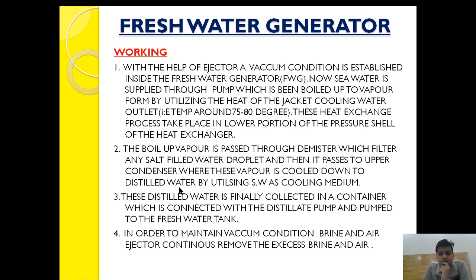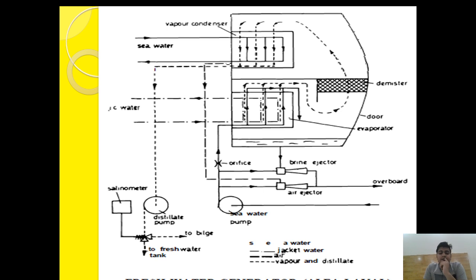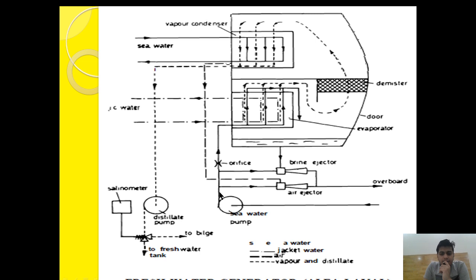After passing the demister, the vapor is passed to the upper condenser where it is cooled down to distillate water by utilizing sea water as the cooling medium. The sea water from the sea water pump also provides cooling for the condenser. The vapor temperature is around 60 to 80 degrees Celsius and it is cooled by sea water having a temperature of 25 to 35 degrees Celsius maximum, which causes the vapor to convert into distillate water.